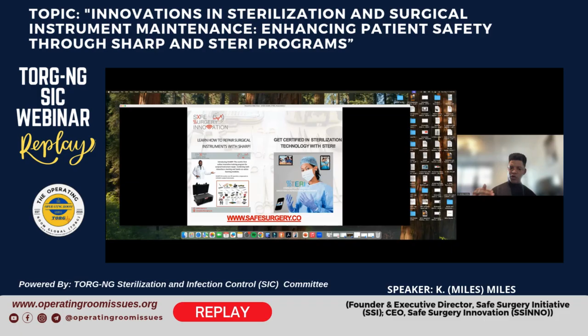So being able to use the right type of testing materials to test each one of those types of surgical instruments. What the SHARP and STERI program both do is not only do we teach you how to use the IFU testing standards, but we also teach you how to use alternatives that are locally readily available in your environment. For instance, instead of using the standard testing material for a scissor, which is a latex resistant band, you can use a surgical glove or a surgical gauze. So depending on what you have available, you can use those different types of things. So for each category of surgical instrument testing, there's an alternative, locally available resource that you could use to perform those tests.